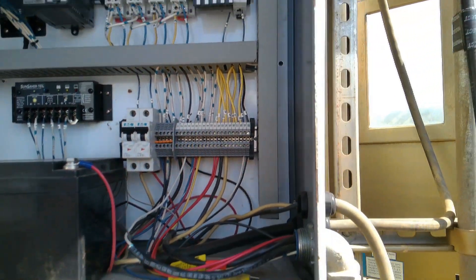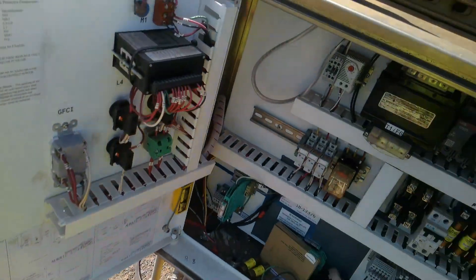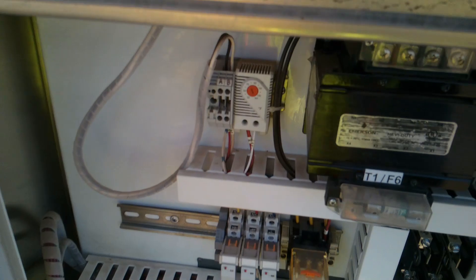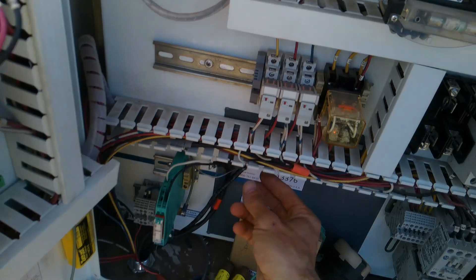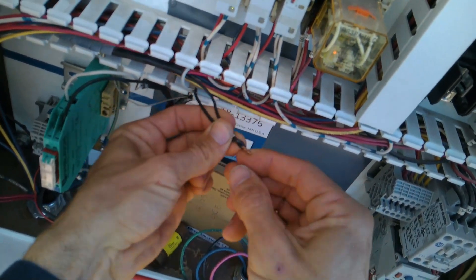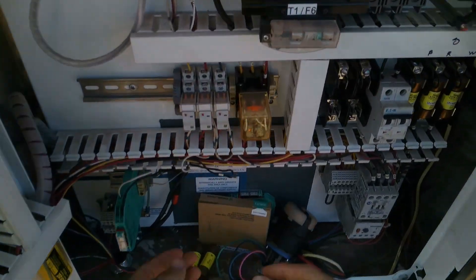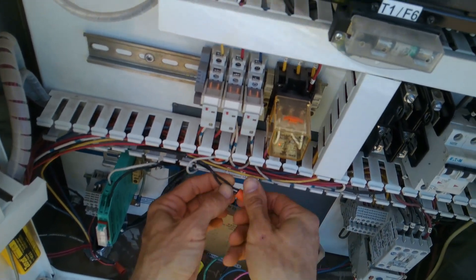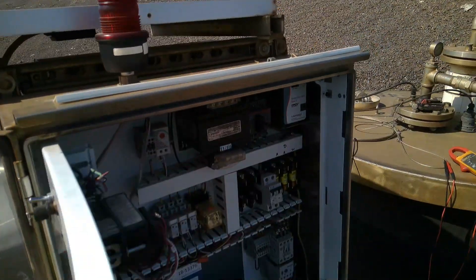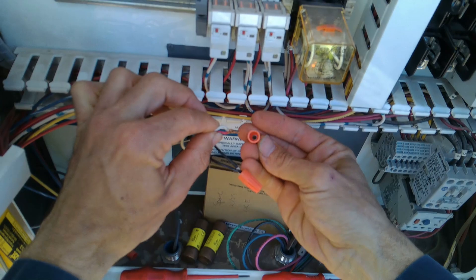So from here this straight black shielded twisted cable goes back over to our local control panel, comes up into this wireway. It does splice in this wireway — let's check that connection, that looks okay. If you open that up, there's your negative number right there — so if one of these connections was bad, that would cause what they're seeing. Let's just make sure that's good and tight. Yeah, that looks good. And then from here it's also spliced up at this terminal — let's make sure that looks good. Yeah, he's all right.